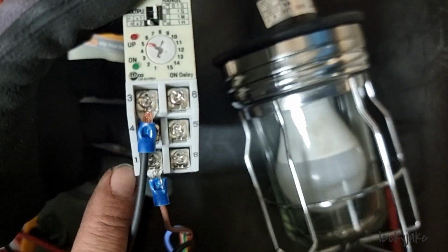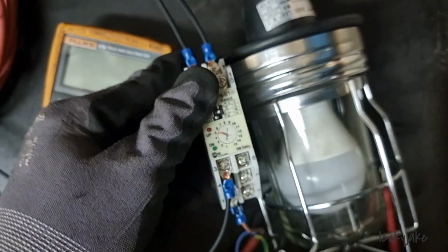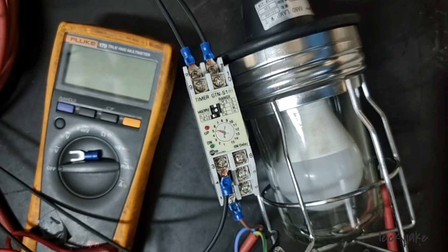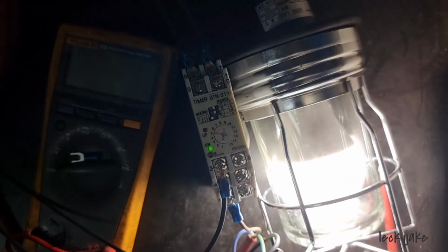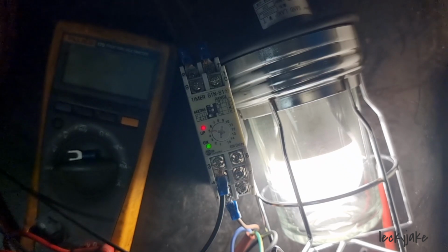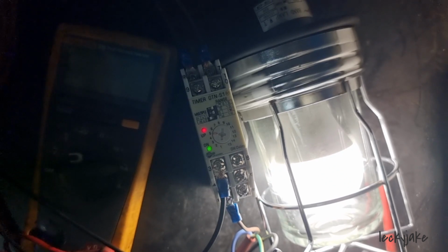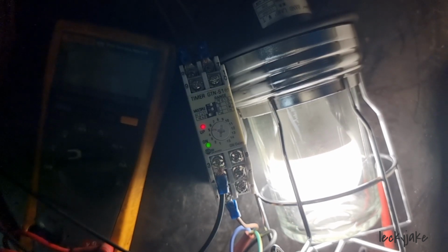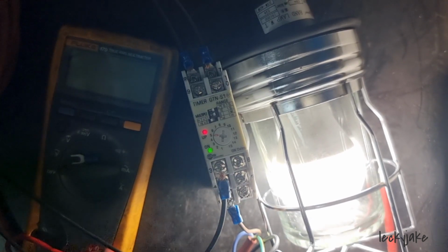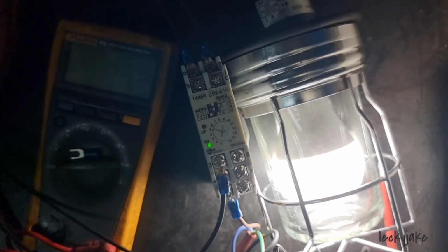Now we transfer the wiring to terminals number 1 and 3 and we will activate the timer again. This operation will only switch the terminals from 1 and 4 to 3 as soon as the timer is activated, without even counting. So it means it is only being used for switching. That is the other application of these timers for terminals number 1, 4, and 3. The load will stay on as long as the timer is on and will be off as soon as the timer is deactivated.